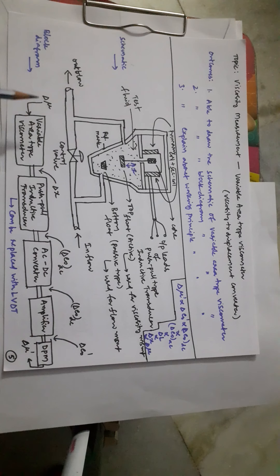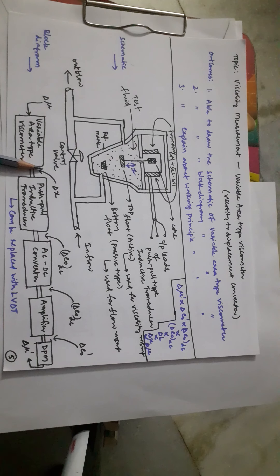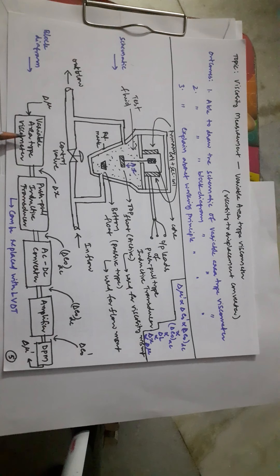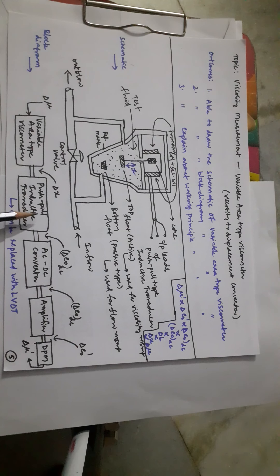The block diagram shows the variable area type viscometer converting viscosity energy to displacement energy. This displacement is measured by a position-measuring transducer — either a push-pull inductive transducer or an LVDT (Linear Variable Differential Transducer). The variable area type is the primary transducer, and the push-pull inductive transducer or LVDT serves as the secondary transducer. Both give an AC output voltage.